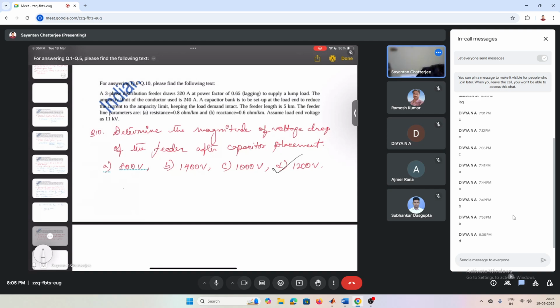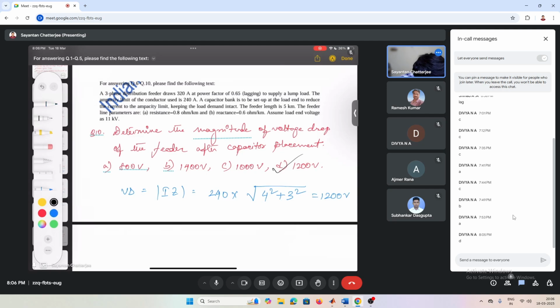So just the voltage drop, you can see, voltage drop is I Z magnitude. After capacitor placement the current would be 0.8 into 5. Feeder length is 5 kilometers, so 0.8 into 5 means, and this is 0.6, same values kind of same, 240 into 5, that will be 1200 volt. So this is the correct answer.